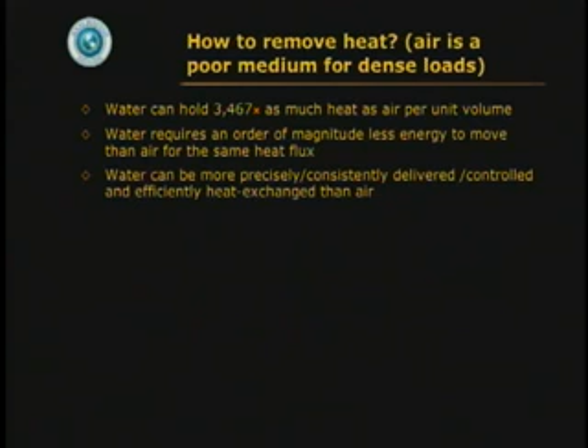So how do you remove heat? Well, now that we have these dense loads in computer centers, air is not a very good way. Air holds 3,500 times less heat than water per unit volume, and water needs an order of magnitude less energy to move than air for the same cooling effect. And you can much more precisely and consistently deliver, control, and heat exchange the water than the air. And yeah, you can mix electricity and water. We used to do this all the time decades ago. Many industries still do. And actually, you can just heat pipe or conduct the heat out to the backplane and then have liquid cooling there, or run a heat pipe straight up. There are other tricks you can use.